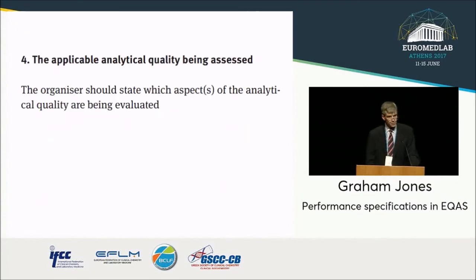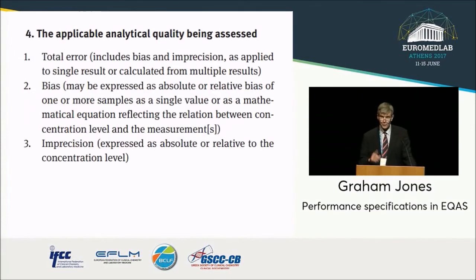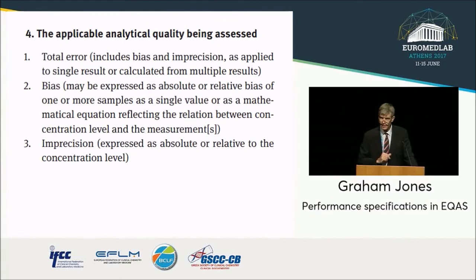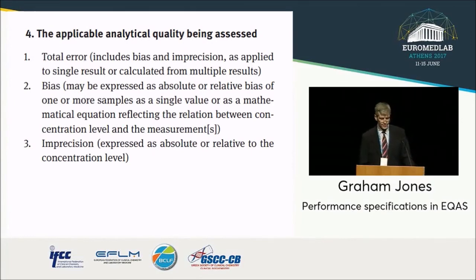The fourth element is the analytical quality property being assessed. If it's a single sample, it must be total error — all of those things are combined. If you're assessing bias, that must be determined from an assessment of multiple samples and taking an average, and a bias specification is likely to be different to a total error specification. Similarly, a specification for precision is likely to be different to both of the above.